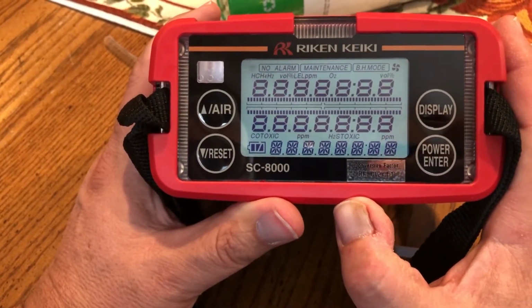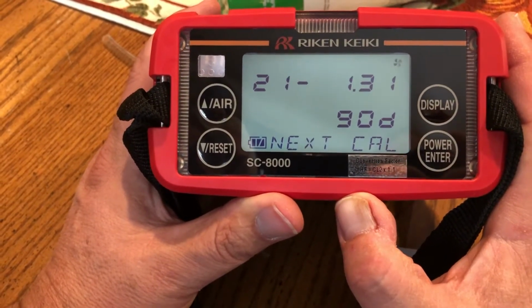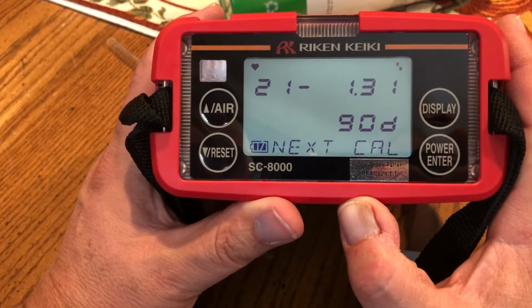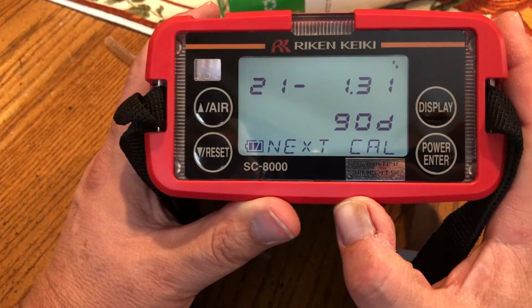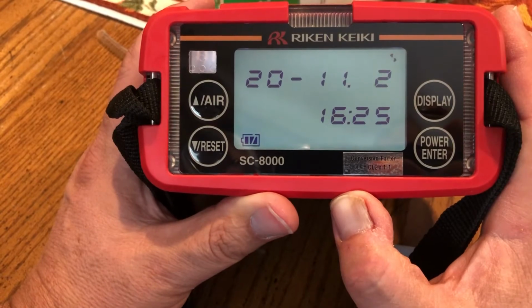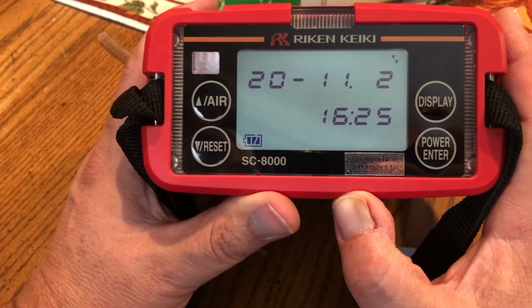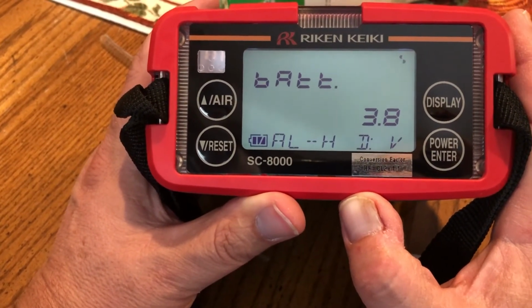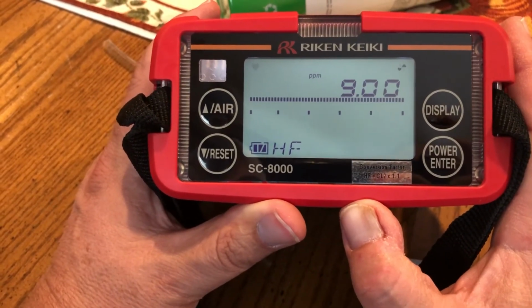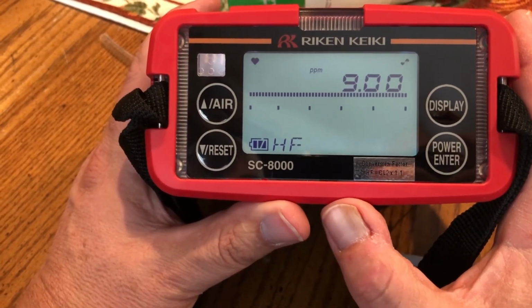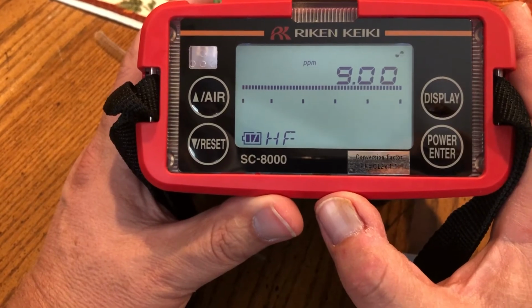The unit is calibrated and it has passed. You have 90 days until the next calibration. That value, 90 days, can be changed to any number of days you like. It would then present the end user with a cal limit identifier if in fact they went beyond the number of days that you desire to be calibrated in.